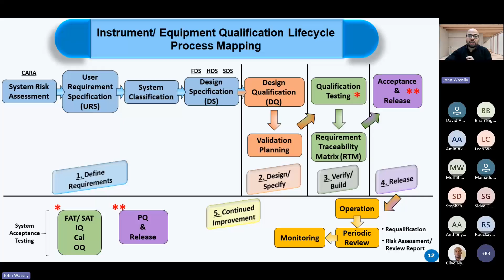Here I'm presenting to you the same stages that we presented through the previous slide. First of all, the validation master plan is the overall organizational approach to system validation, including the deliverables, personnel, testing strategy, and general acceptance criteria. This is the main umbrella document under which I will be stating all the qualification activities that should be done for each piece of equipment or any system. Okay? And then going through the URS, the user requirement specifications that we presented through the previous slide. In this, we will define all the requirements that we need as users to be fulfilled through the piece of equipment that we are going to purchase.